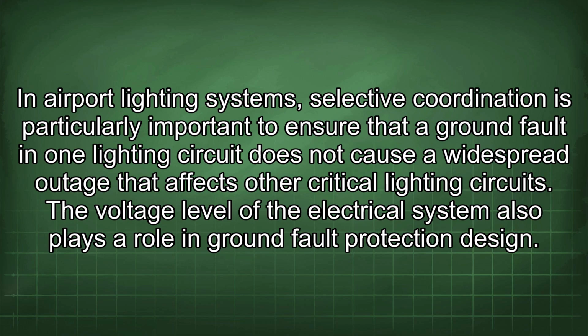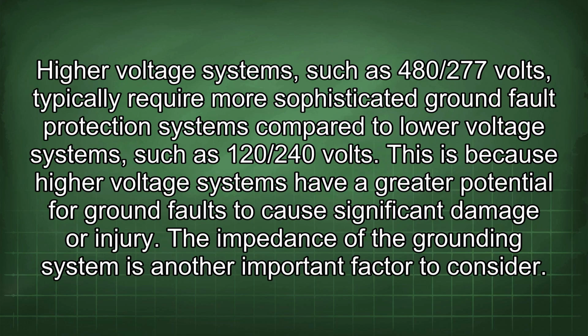The voltage level of the electrical system also plays a role in ground fault protection design. Higher voltage systems, such as 480/277 volts, typically require more sophisticated ground fault protection systems compared to lower voltage systems, such as 120/240 volts.